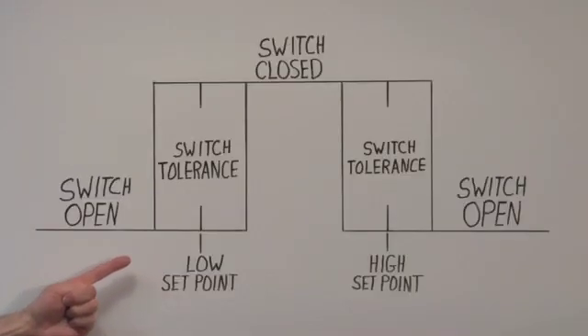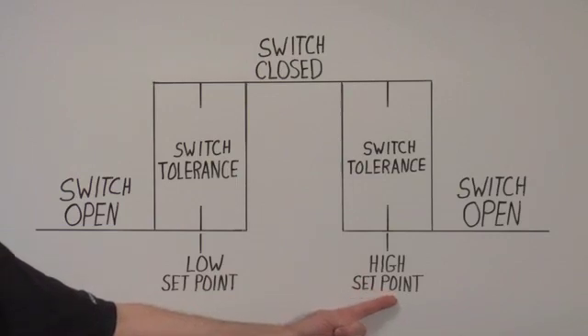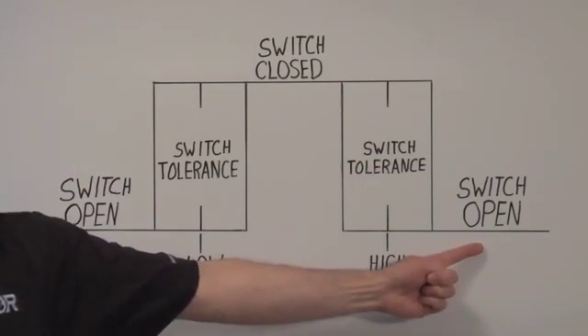This diagram depicts the windowed or default switch point type. The functionality is simple. The switch is off or opened when the process pressure is less than the switch low set point, or if the process pressure is greater than the switch high set point.